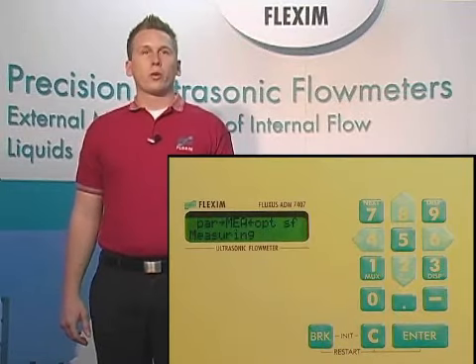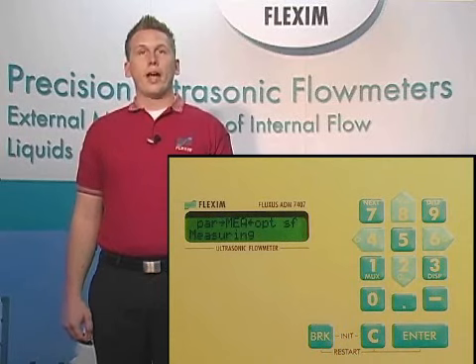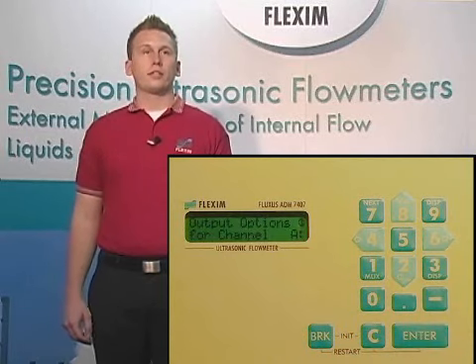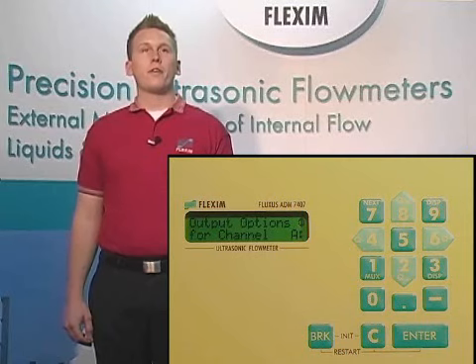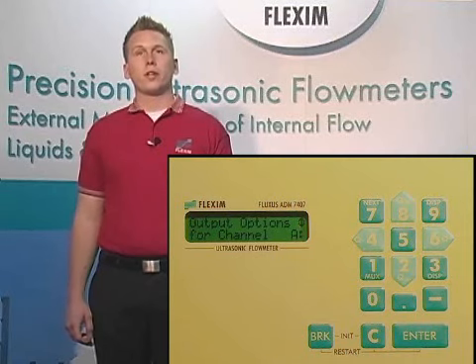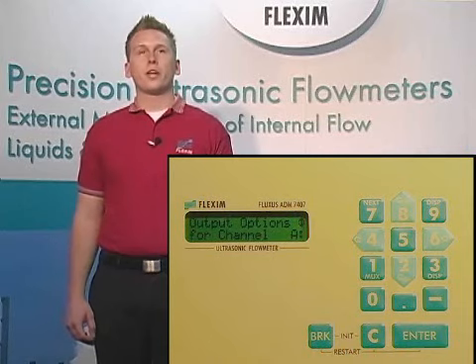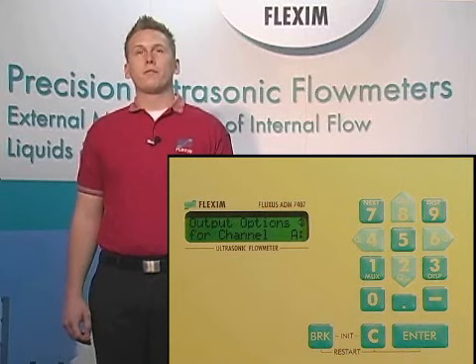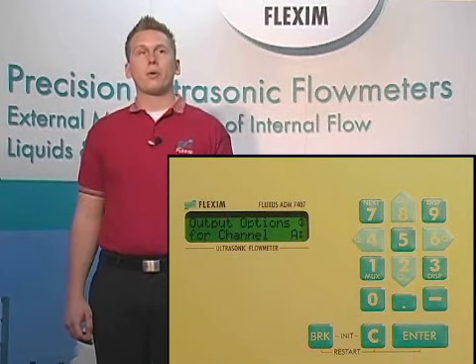Lastly, we're going to look at the output options menu. You'll want to access the output options menu if you need to change any of the default values. Let's begin by scrolling over to the output options section labeled out on your main screen and hit enter. The first thing we have here is again a choice of the channels we'd like to set up output options for. Just like in parameters, we have options of setting channels A, B, Y, or Z. For now, let's configure just the A channel since most of you are probably interested in single point measurement.